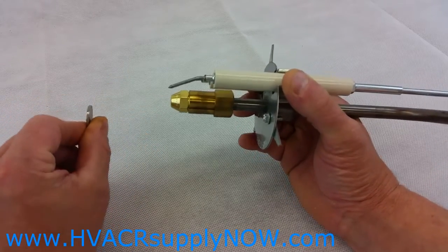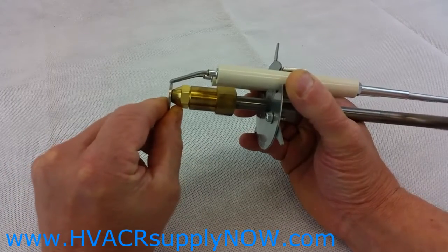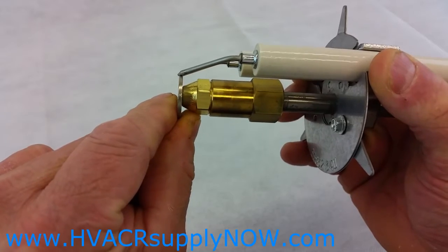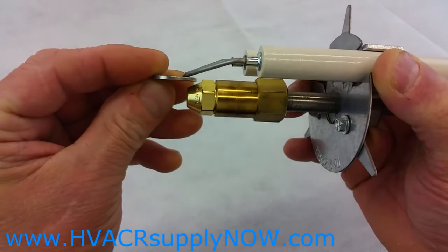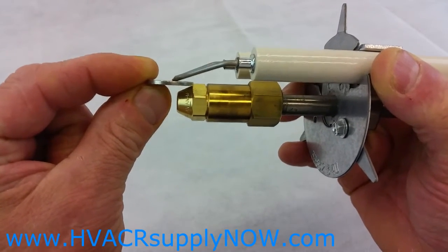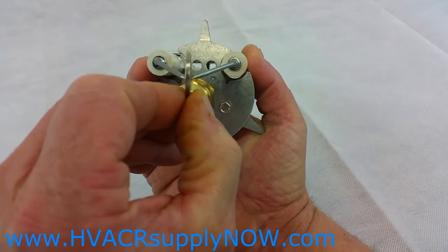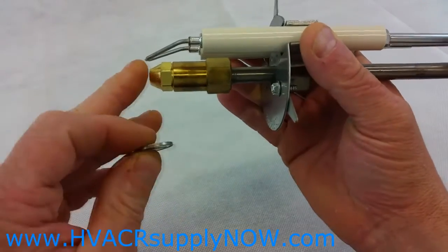The nickel trick involves three measurements. First, you're going to measure the head of the electrodes — that'll be one nickel. Next, the height of the electrodes — again, one nickel. And lastly, the gap of the electrodes — that'll be one nickel. That's the nickel trick.